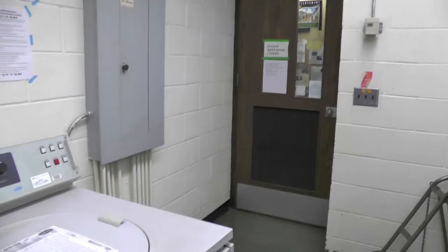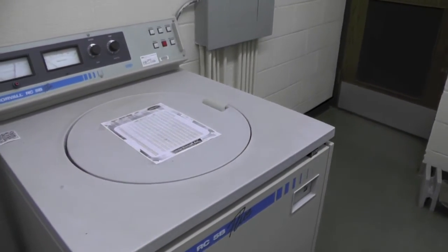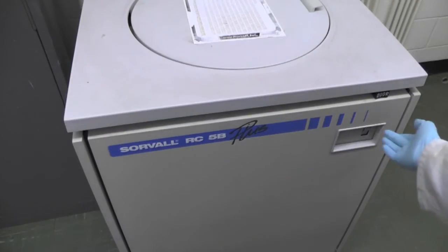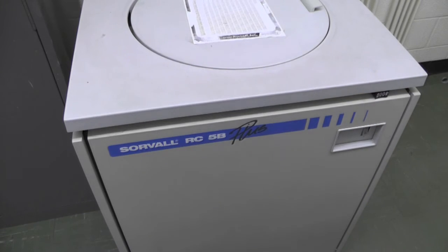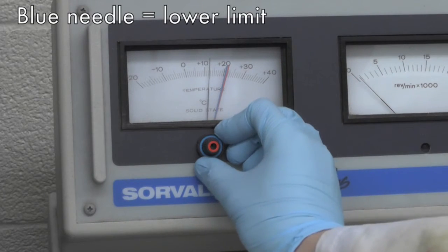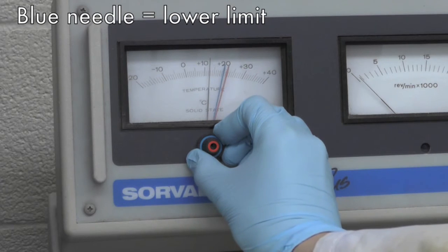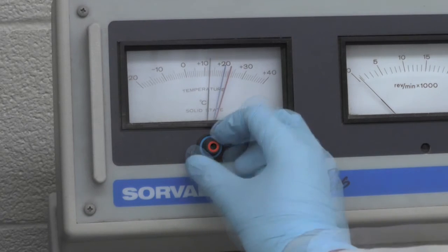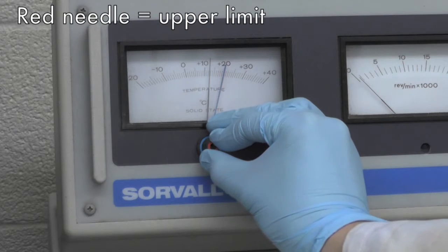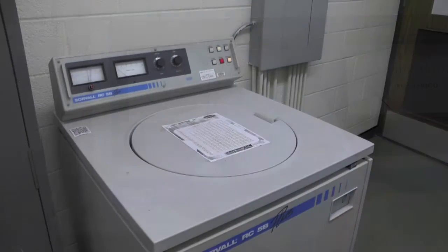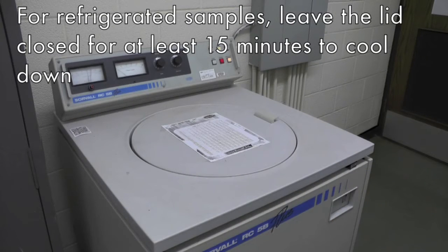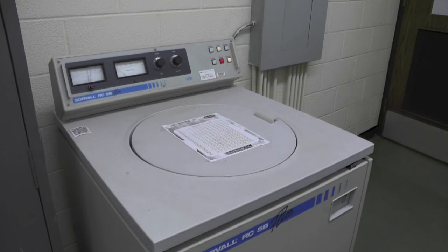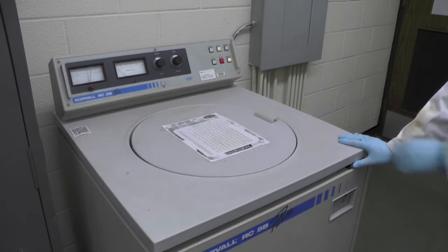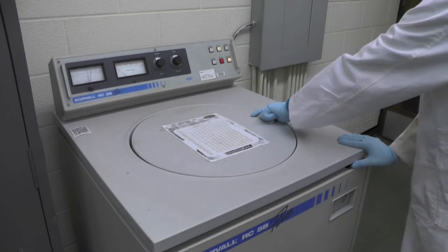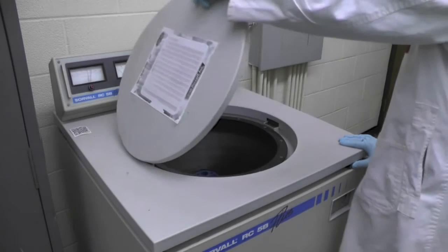This is the Sorvall RC5B refrigerated superspeed centrifuge. First, turn on the power. To set the desired temperature, adjust the blue needle, which is the lower limit, using the outside knob, and the red needle, which is the upper limit, using the inside knob. Note that if using refrigerated temperature, close the chamber door and let cool for at least 15 minutes. To open the chamber door, press the door button at the front of the instrument while lifting the door at the same time.